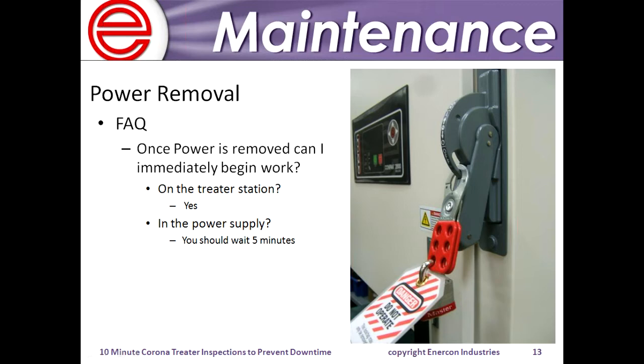You can basically work on it right away. There's no charge stored in the high voltage transformer or anything like that, because once the power supply is shut off, there's no chance of the inverter firing. The primary side of the high voltage transformer is basically just a coil that's shorted, so you have a short circuit on the input, and there won't be any charge left on the output.